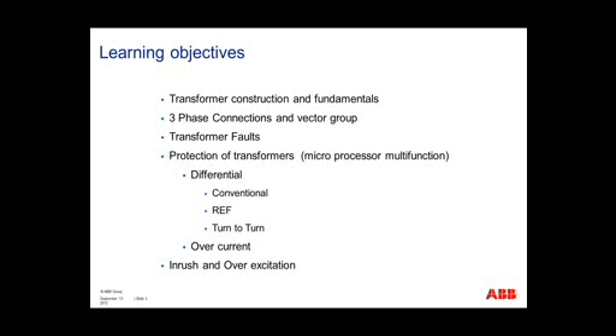So the learning objectives for today. We're going to be talking about the transformer construction and fundamentals, three-phase connections and the vector groups. We're going to go over different types of transformer faults, how they occur and how they look. We're going to go over the protection of the transformers. We're going to stick with microprocessor-based multifunctional relays. We're going to touch a little bit on some of the solid-state relays, however, and see how they used to do it and some of the benefits of going to a microprocessor-based relay on your transformer protection. We're going to look at conventional differential protection. We're going to look at restricted earth fault protection, turn-to-turn fault, overcurrent, inrush, and overexcitation.